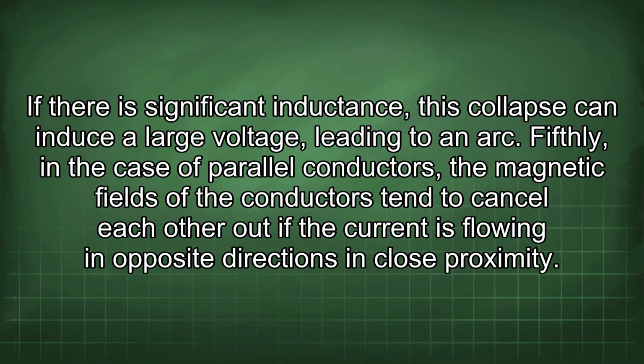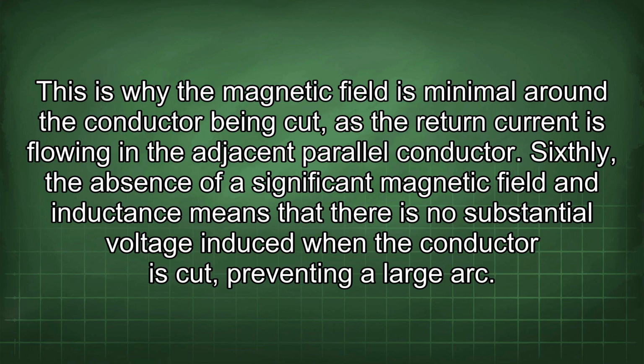Fifthly, in the case of parallel conductors, the magnetic fields of the conductors tend to cancel each other out if the current is flowing in opposite directions in close proximity. This is why the magnetic field is minimal around the conductor being cut, as the return current is flowing in the adjacent parallel conductor. Sixthly, the absence of a significant magnetic field and inductance means that there is no substantial voltage induced when the conductor is cut, preventing a large arc.